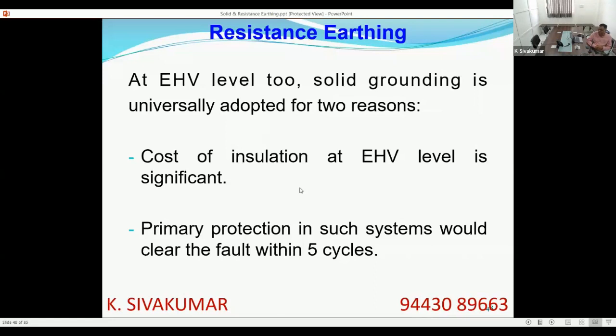The second thing is, yes, current is a fault detection criterion, but generally all EHV systems will have unit protection. It is mandatory. It will have unit protection like differential or restricted earth fault or bus differential. These systems are instantaneous. You cannot build up any intentional time delay in these unit protection schemes. They are capable of clearing the fault within 100 milliseconds or 5 cycles. So a fault shall not be kept in the system for a longer period because you have a dedicated unit protection scheme. This is mandatory for EHV. So generally EHV people go for solid earthing. The advantages of solid earthing outweigh the disadvantages, so they go for solid earthing.